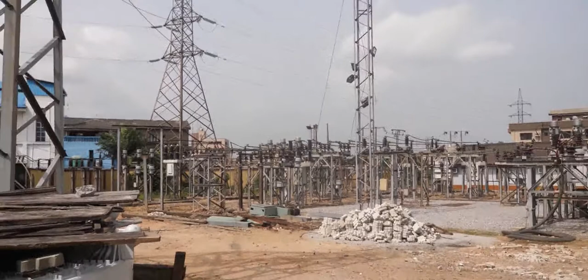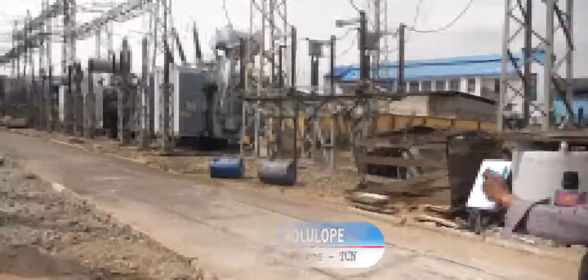At the Maryland substation, the Senior Manager System Operations Engineer said in an interview that the substation has 4 lines connecting to it. There are 2 lines coming in from Ikorodu substation, while 2 others feed the substation from Ikeja West and Akangba substations. All these fall on a 132 kV bus bar from where the 3 power transformers take their supply.